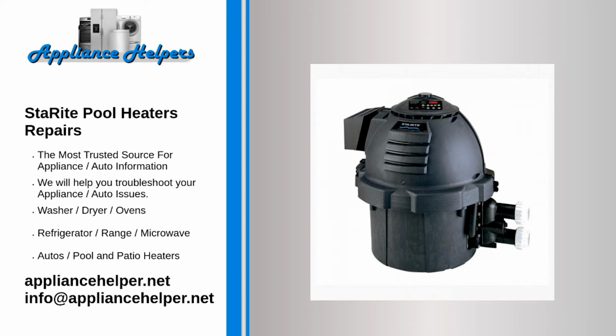This includes the switch on the heater and the main power supply breaker for the heater. Ensure that all valves are in the open position. This includes the gas valve, gas supply valve, plumbing, and filter valves. Make sure the pilot light is lit. If it isn't, continue to the following gas pool heater troubleshooting step. Make sure the thermostat is set to a higher temperature than the current water temperature. If you are using pool automation controls to set your water temperature, check that also.